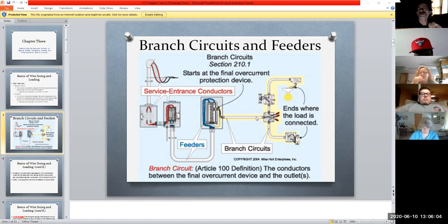I have one main line coming through to a junction box here being fed out. And so when it spreads out like that, that's considered the branch. It's still all tied back with one circuit, but here we're feeding several different things. So the conductors between the final overcurrent device and the outlets, that's considered your branch circuit here. So basically my wiring feeding into this is essentially considered the branch, if you will.